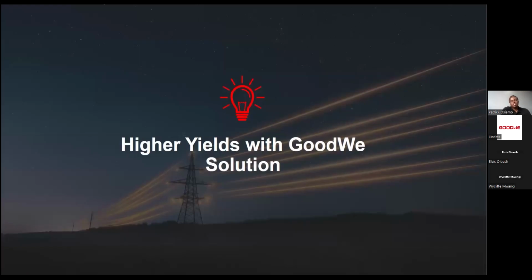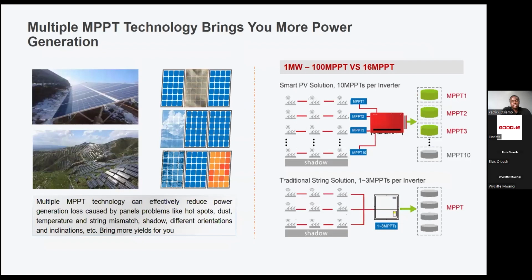In case you want higher yields for your PV system, again, GoodWe can provide such a solution. Reason being, we have numerous MPPTs, from 2 up to 12 MPPTs. And how to utilize this: with the different MPPTs, you can have strings, unfortunately, covered by dust. Unfortunately, the plants are big, so part of it is covered by cloud cover, or part of the modules are overheating, or there are some cell damages. These strings will be working independently and not affecting the rest of the PV.